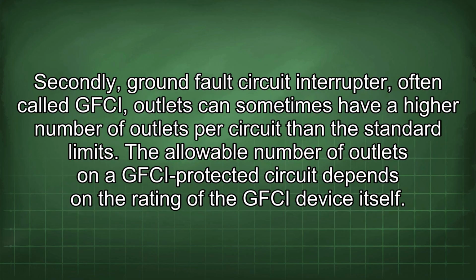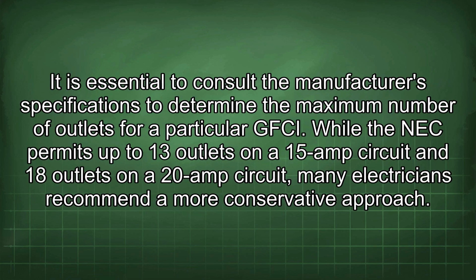Secondly, ground fault circuit interrupter, often called GFCI, outlets can sometimes have a higher number of outlets per circuit than the standard limits. The allowable number of outlets on a GFCI protected circuit depends on the rating of the GFCI device itself. It is essential to consult the manufacturer's specifications to determine the maximum number of outlets for a particular GFCI.